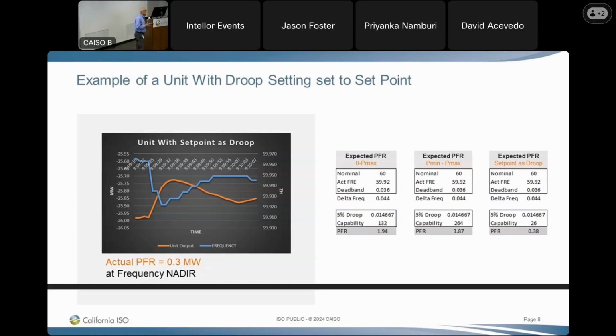And I've got 3 different scenarios that are very common in California: the 0 to Pmax, the Pmin to Pmax, and a set point as droop. What set point means is that wherever the unit is operating at the time of the frequency event, the capability of the unit is calculated as wherever it's operating. If it's a 100 megawatt unit, and this was actually larger than 100 megawatts, it's a 132 megawatt unit, then the capability of the unit for the purpose of providing frequency response is looked at where the set point is, which is at this point about 26 megawatts. So you're shortchanging the interconnection significantly by putting your setting at set point.